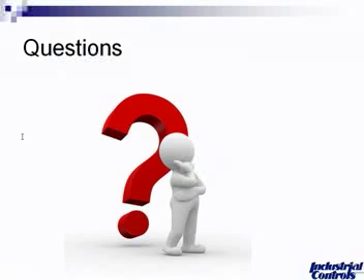Okay. Another question we received is from Ariel. What is the best recommendation for a flash tank? Best recommendation for a flash tank would be a float and thermostatic style steam trap. You will have flash present, you'll have varying pressures present, you'll have varying loads present.